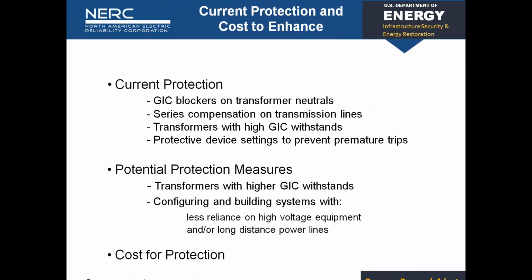Let's see what else. Okay, another thing you can do is put static or active grounding devices from the transformer neutral to ground connection. You also, as I said, could, as you put new transformers in, ask the manufacturers to build them with high GIC withstands. Those two exist. The delta connected transformer windings are less susceptible. Again, very few have been ordered that way because people weren't worried about that. So as you replace old transformers, it's legitimate to think about building in your withstand as opposed to attaching a protective device to it. And as Mark also mentioned, adjusting protective device settings is important to prevent voltage collapse.